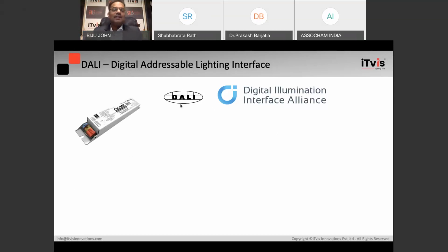But this DALI standard was only for electronic control gears. That's why, if you see the DALI standard, you can always see something mentioned like ECG, and ECG stands for electronic control gear. And before LED, these DALI standards were only for the fluorescent electronic control gear. Now, when LED came into the picture, two types of LED DALI drivers were defined in the DALI standard. Type number 1 is called DALI type 6, DT6. That's the reason people ask, do you have a DT6 DALI driver or a DT8 DALI driver? That DT stands for DALI type. So DALI type 6 and DALI type 8.